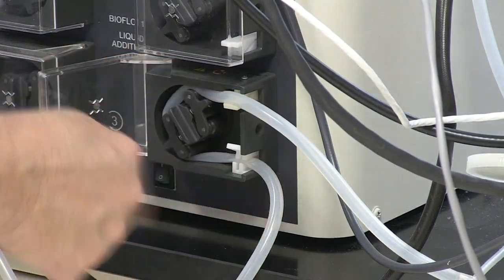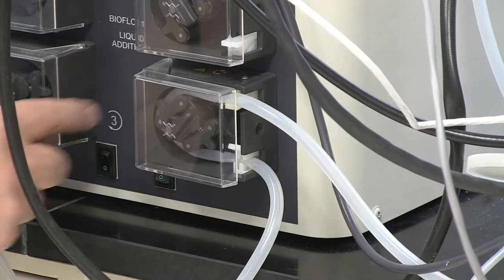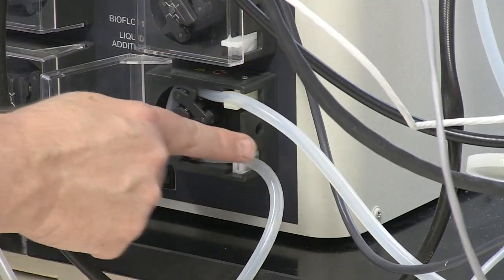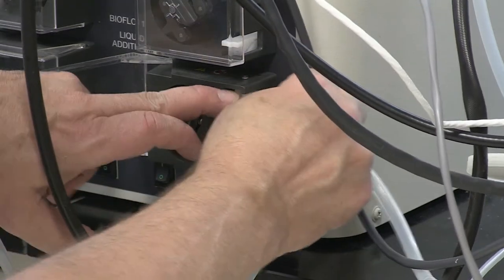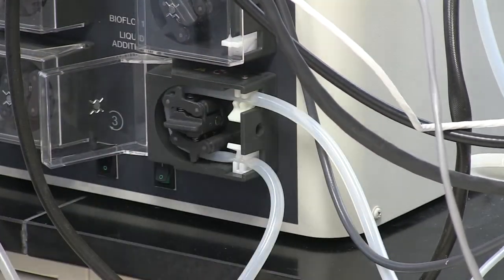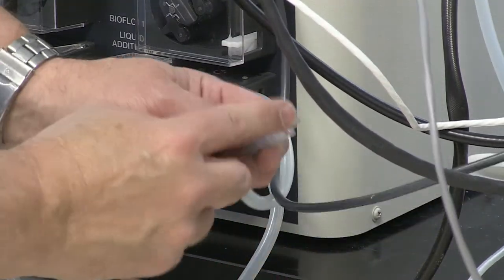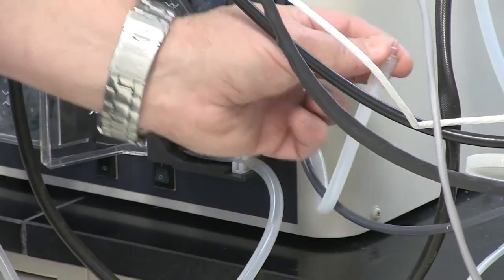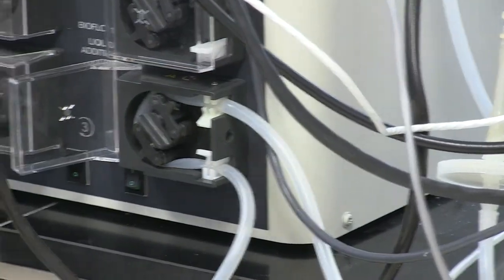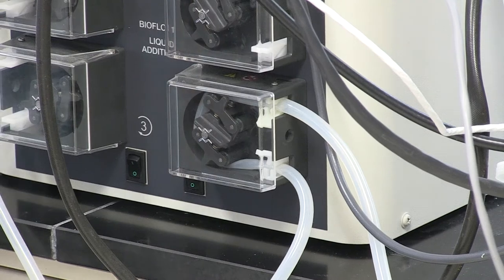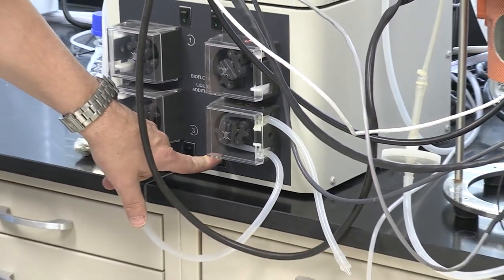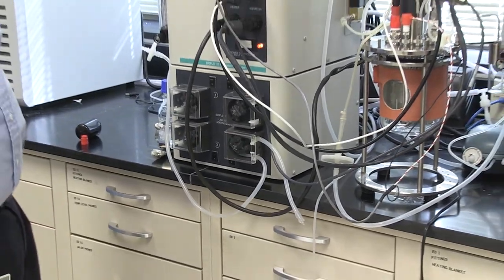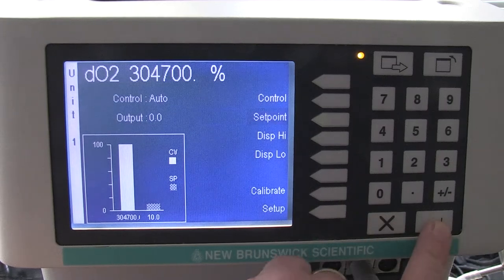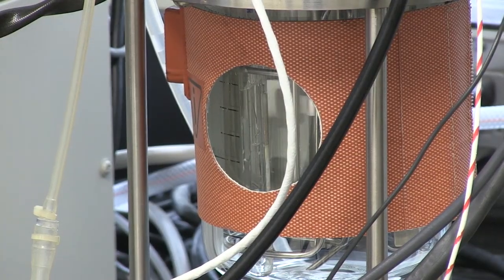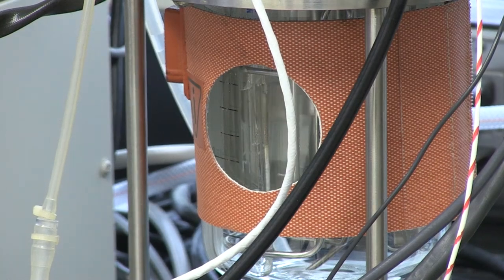Anyway, so you need to see this one is pumping in. This number four is a clockwise pump. So it's coming in here. Whoops, I haven't got it all the way in there. Yeah. So then this would go to a small tubing that would attach, say, to your auxiliary port to add your antifoam. So it would only be turned on when it needed that to be pumped. So this unit has potentially four different liquid additions that it could do.